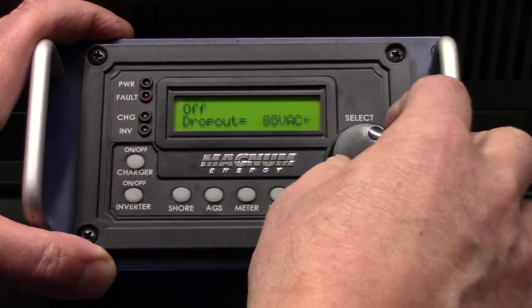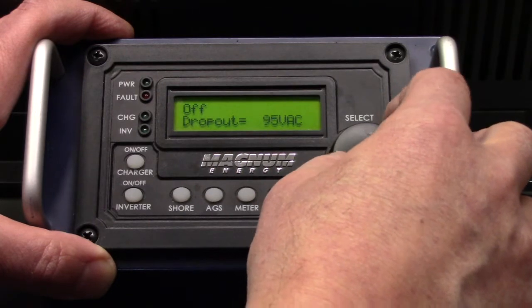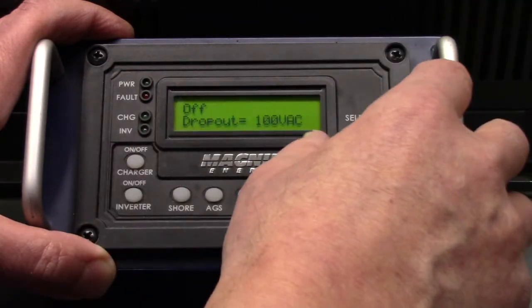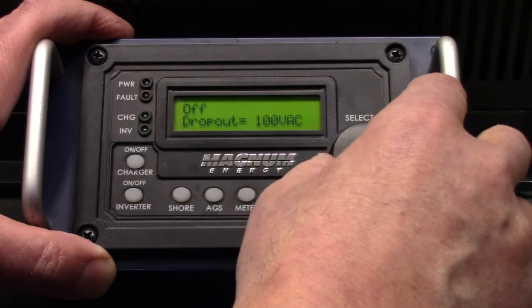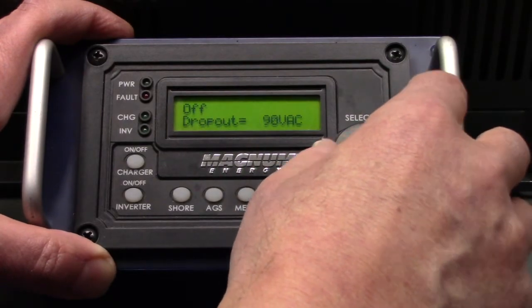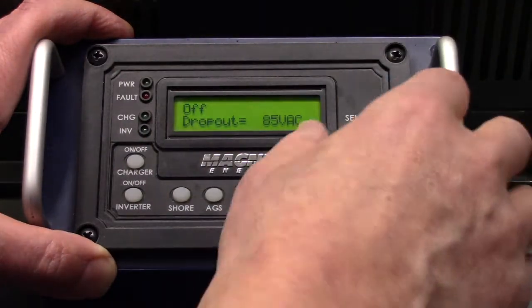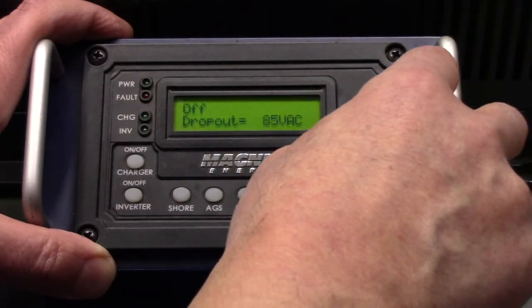And if for some reason you want it to cut out sooner, you could set it up to maybe 100 or so, 95, and all that would do is if you get a power sag, it would go ahead and shut off the battery charger.